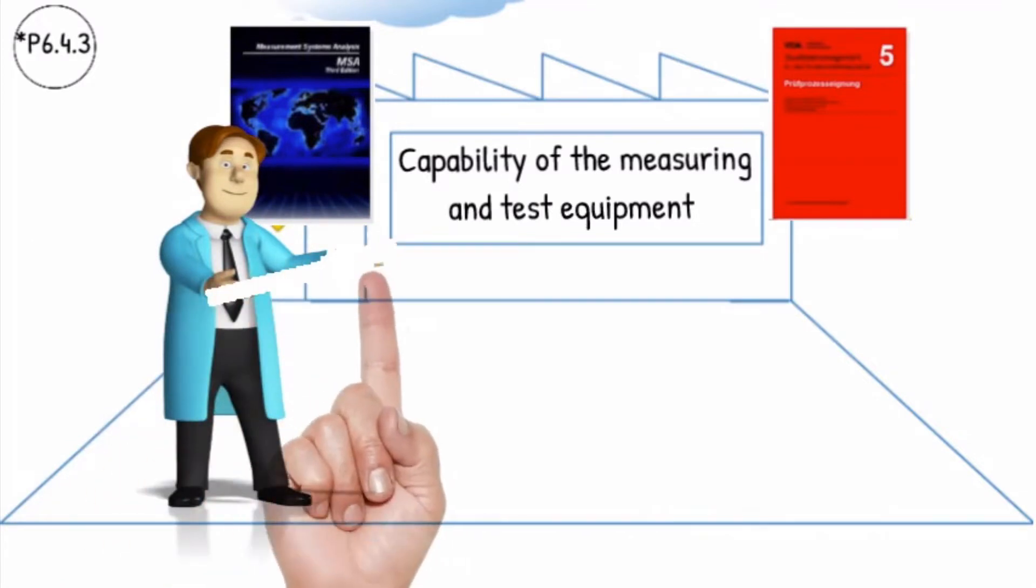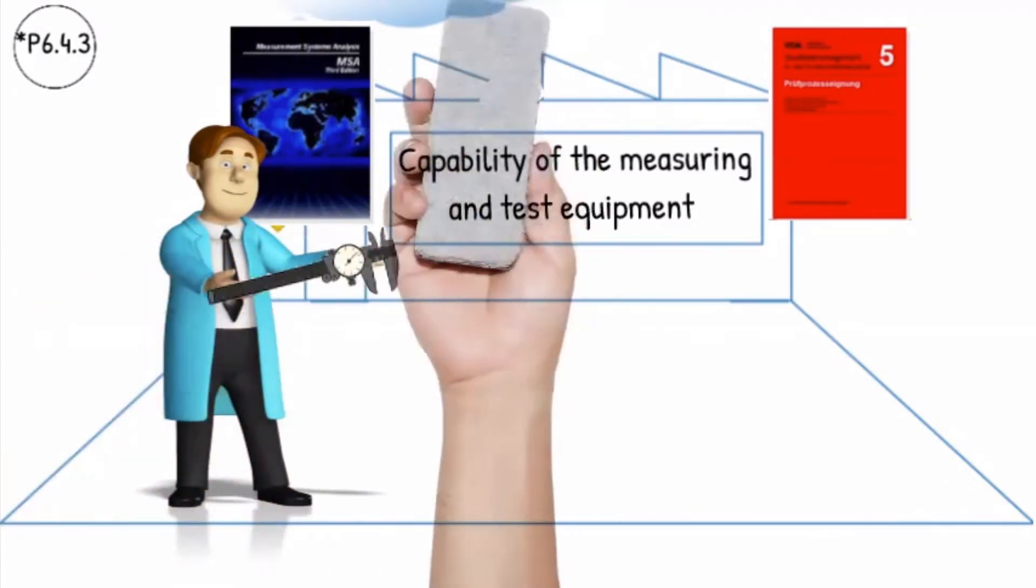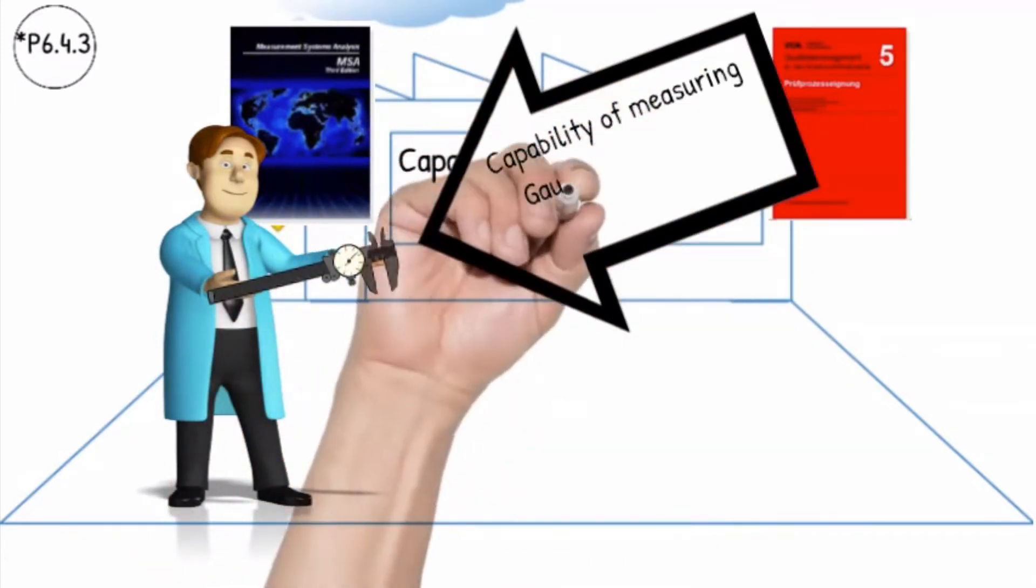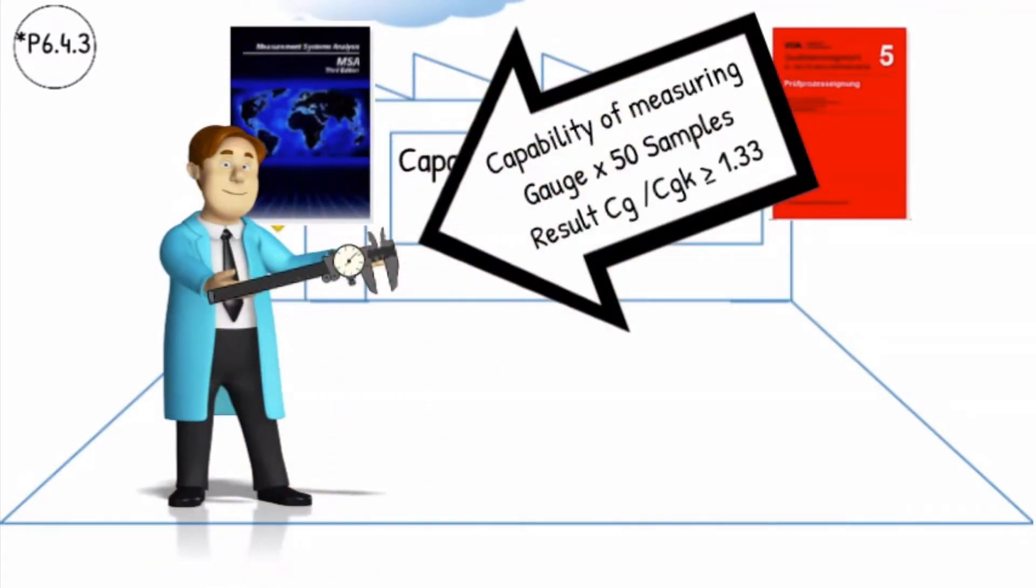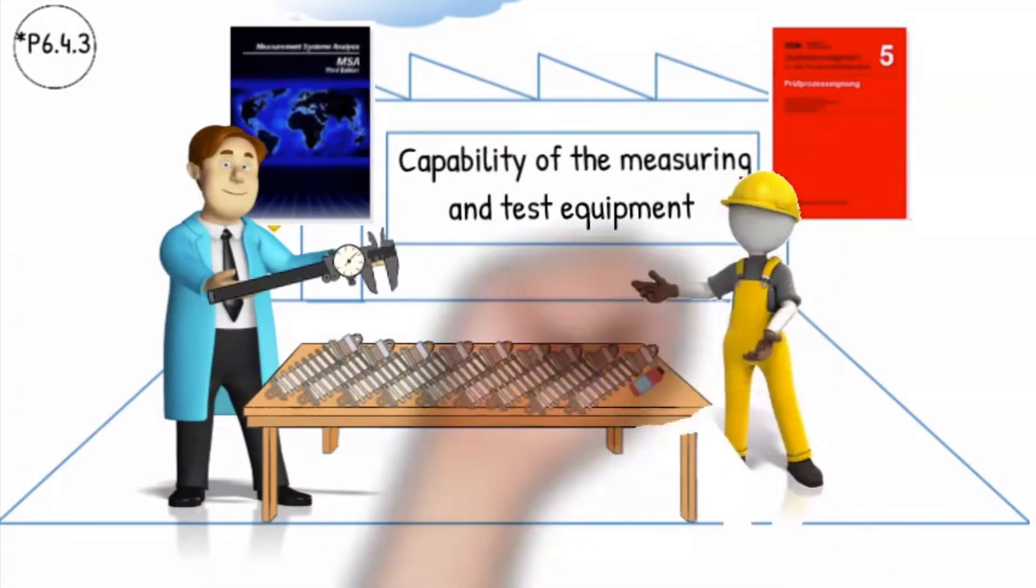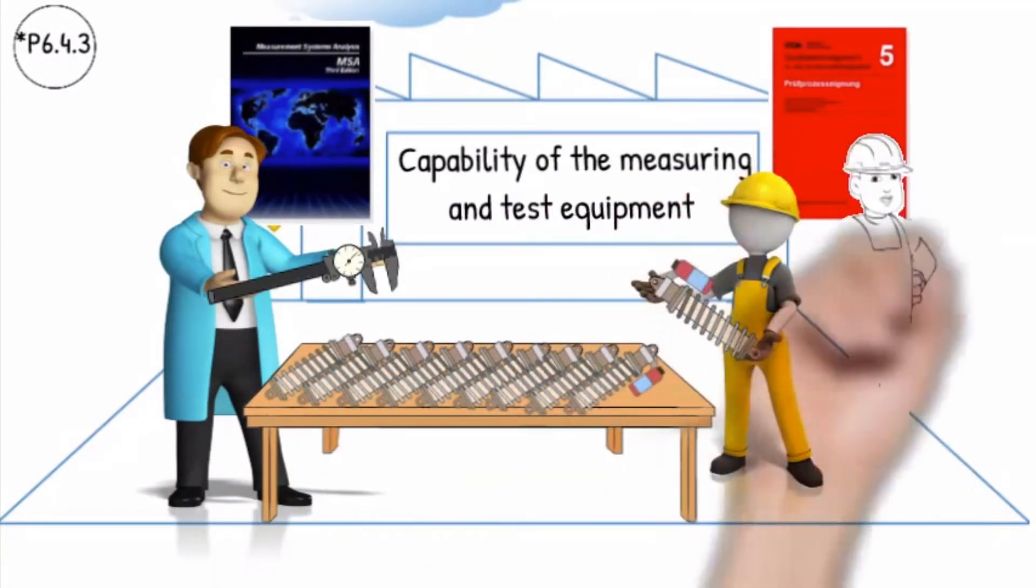The first step is to determine the capability of the test equipment. You need to measure 50 samples and the CG and CGK result must be equal to or larger than 1.33. The second step is to do a Study 2 evaluation to determine the repeatability and the reproducibility study which includes the operator influence.